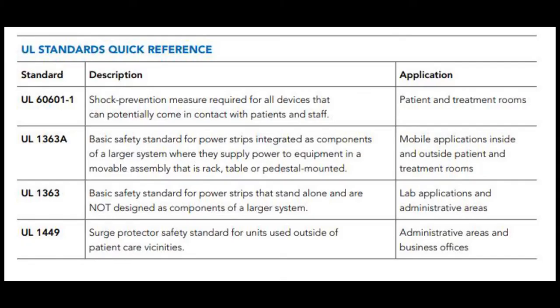There are four kinds of power strips allowed in medical facilities. Each is required to have a hospital-grade cord and plug, as well as hospital-grade receptacles, but they differ in mounting requirements and electrical protection circuitry.